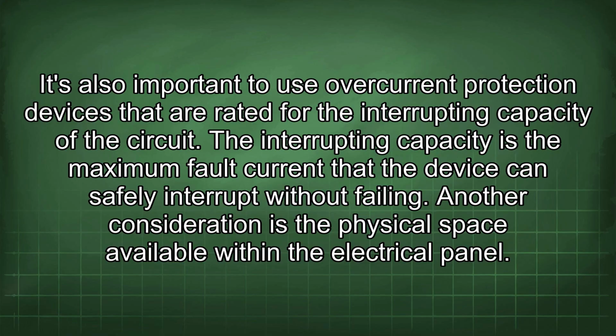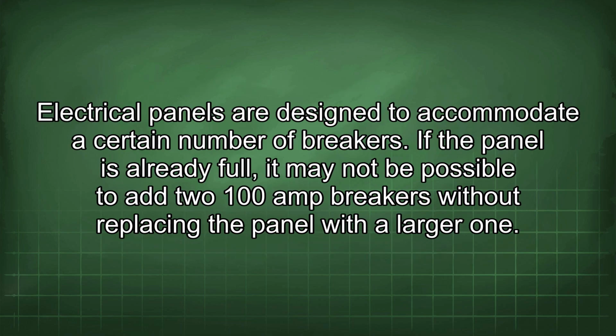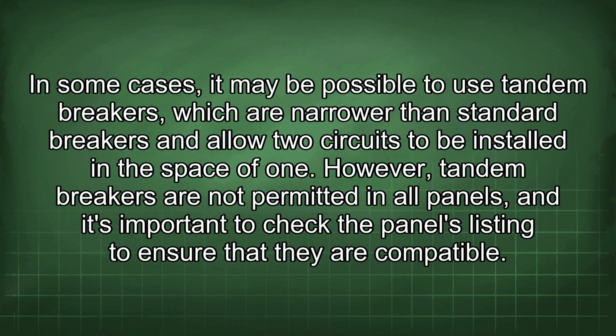Another consideration is the physical space available within the electrical panel. Electrical panels are designed to accommodate a certain number of breakers. If the panel is already full, it may not be possible to add two 100-amp breakers without replacing the panel with a larger one. In some cases, it may be possible to use tandem breakers, which are narrower than standard breakers and allow two circuits to be installed in the space of one.